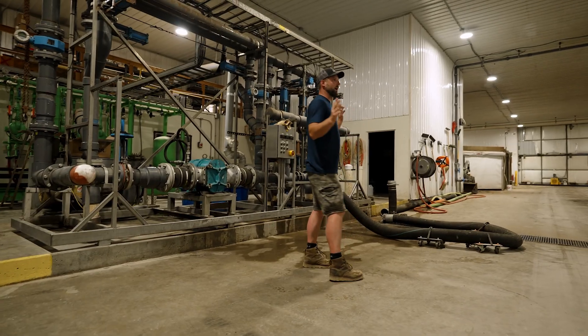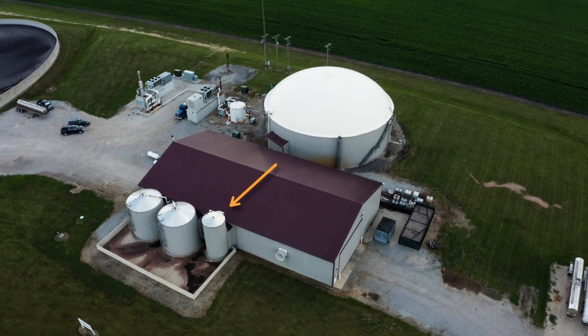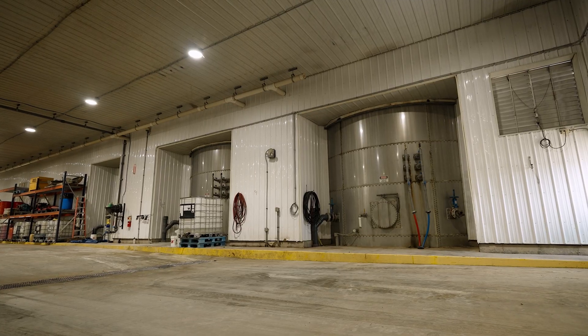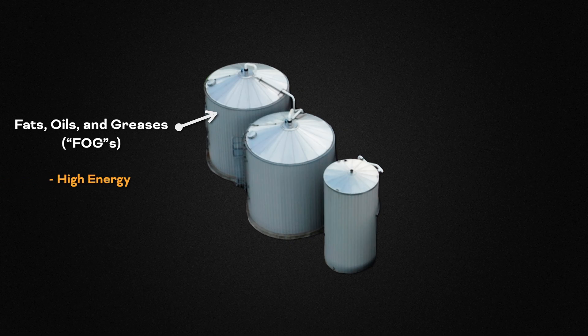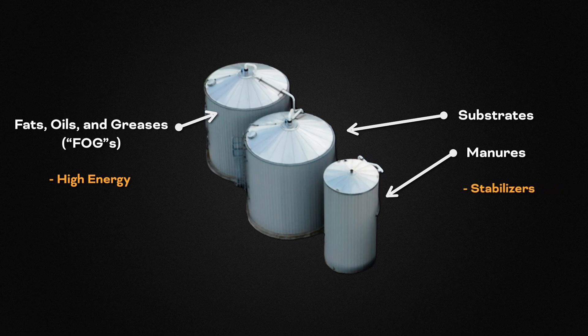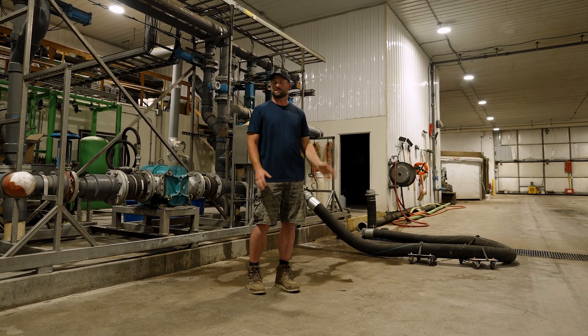The products coming in are largely manufacturing food waste. Right now the economy is that they pay us to take it. Products from the trucks go to one of three tanks. The first is a steel 20,000-gallon tank — that's our manure tank, primarily hog manure, sometimes dairy. Then two stainless steel tanks at 50,000 gallons each: we call them the substrate tank and the FOG tank. FOG stands for fats, oils, and greases, which are more high-energy per gallon. The others are more like stabilizers. We always call the manure the Pepto-Bismol — it's kind of keeping things equal. It's really all just a big stomach. You want a steady diet of consistent products with minimal variability, and we use our manures to stabilize things so you don't get upset.